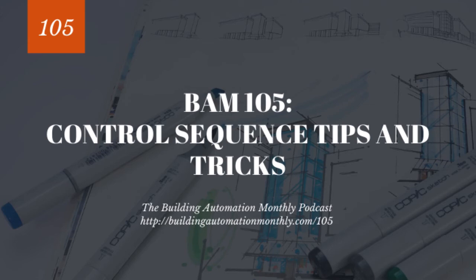That air changes allows us to add volumes of air that are either hotter or colder, either removing heat from the space or adding heat to the space. Well, if our points are wrong, if we're providing too much air at minimum, could we be subcooling the space? And so sure enough, that's actually what happened. It was that the minimum airflow set point was way too high, and they weren't seeing issues during the summer. And this is kind of one of those indicators that will tell you if your CFM for your heating is way too high, especially on cooling only boxes.